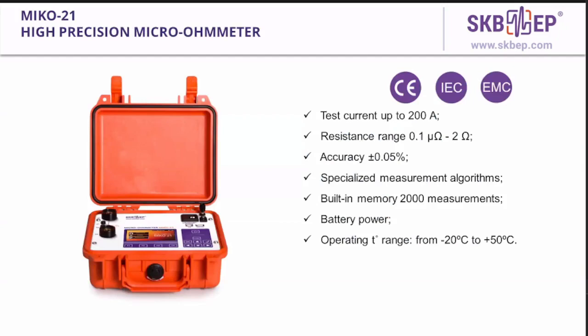Here, let me proudly present one of our top-selling devices. This is a high-precision micro-ohmmeter called MIKO-21. As you can see, the accuracy is 0.05%. It also has built-in memory for 2,000 measurements and a battery power supply. The main feature is that it has a good test current, up to 200 ampere with a step of 1 ampere, and it's very useful when you need to set a particular test current.